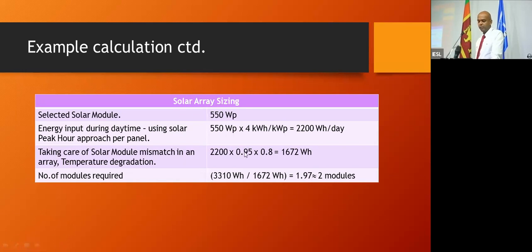From this I'd also suggest you compensate for temperature mismatch and similar losses, because as the temperature goes up, solar panel performance goes down. Honestly, we can get about 5 kilowatt hours, because according to the maps for Sri Lanka, we have about 5 peak sun hours. You can take it as 5, but I've taken 4. What I'm saying is please compensate for temperature losses. In Sri Lanka we'll easily lose 15 to 20% from the rated value, because our nominal operating solar panel temperatures can go up to 45, even 50 degrees.